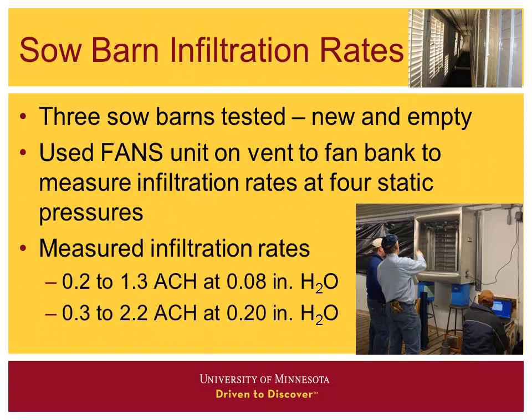My former colleague Larry Jacobson had done some measuring of infiltration in three different sow barns or rooms. They were new and empty. He went out with a blower door unit — a fans unit used to measure flow rates through a chamber — placed on an exhaust vent for a fan room. He measured static pressure and infiltration rates. It's like a blower door test on a house, if you're familiar with those.